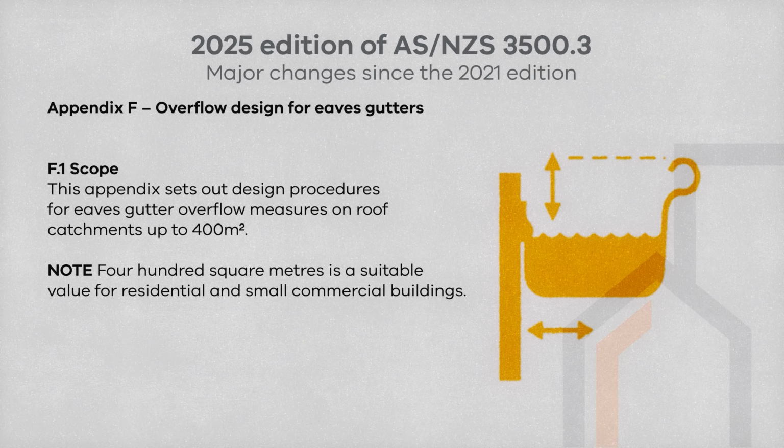If the roof catchment area exceeds 400 square meters, a performance solution is required because this goes beyond the design parameters of the standard. However, to comply with the standard, a plumber can divide the roof into separate eaves gutter systems, provided each system serves a distinct catchment area not exceeding 400 square meters. And the systems are generally independent, not just artificially divided on paper.